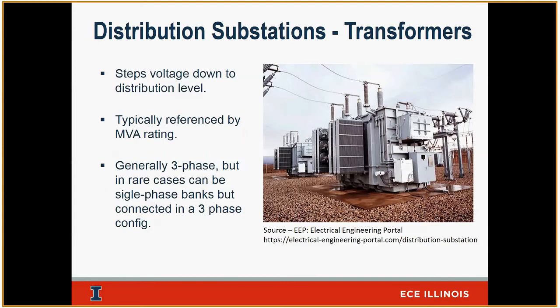Again, you're probably familiar with some of this stuff. Transformers have fans. You can turn these fans on during peak load periods when it's really hot out there. It gives you a little bit more capacity. These are the lines that are coming in from the high side of the transformer, and then the other side will be the load side of the transformer. So the high side will be, for example here, the 69 kV, the higher voltage, and then the load side would be the lower voltage.